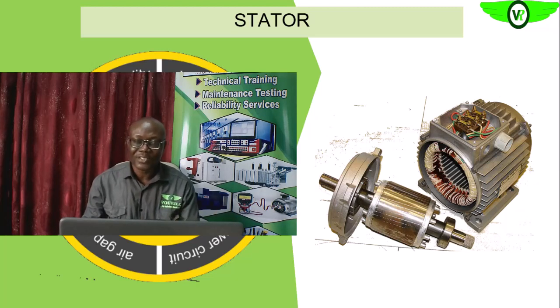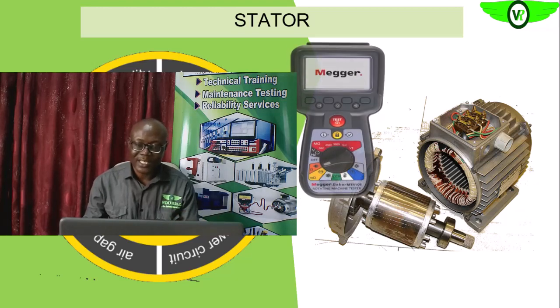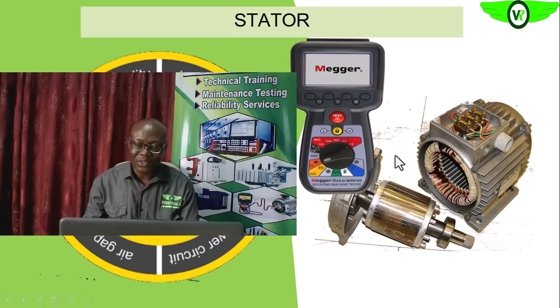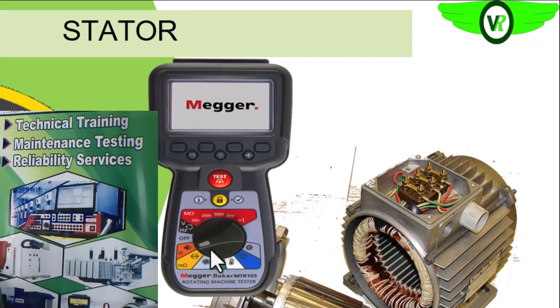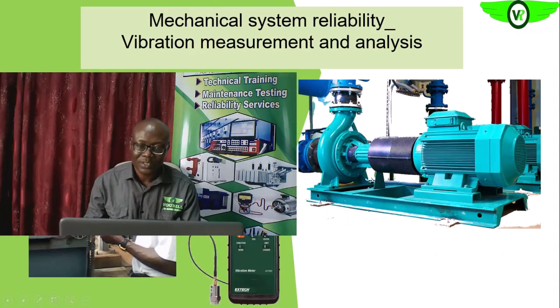You can check out our training on resistance tests and also low resistance winding resistance tests, okay, on electric motor in our earlier section. So the MTR105 can do it. So you see the milliohm selection. You can turn this your selector switch to the milliohm, connect your probe appropriately, then you can test, okay, and do your calculations to see if we have any resistance unbalance.